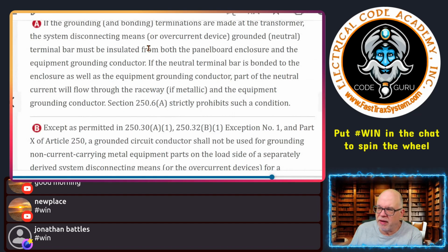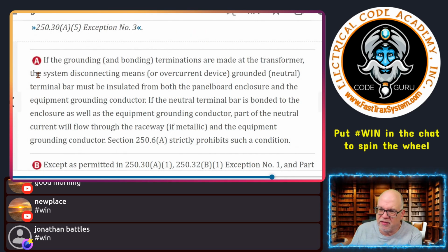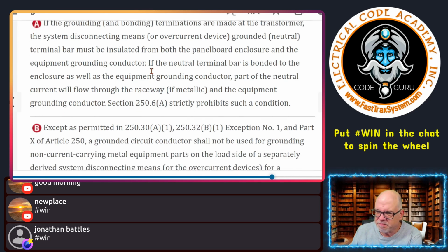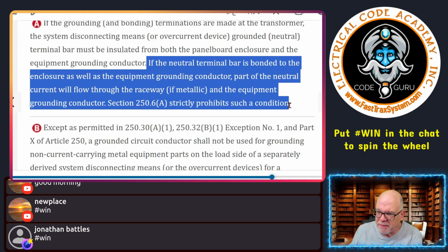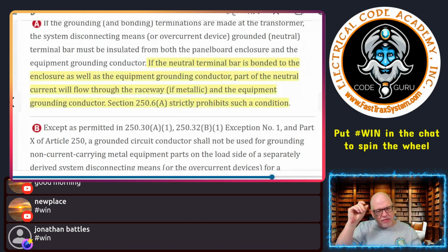It says, if the grounded and bonding termination is made in the transformer, the system disconnecting means grounded neutral bus must be isolated from both the panel board enclosure and the equipment grounding conductor. So it's isolated. Y'all got that. We just covered that. Okay. Again, if you do it improperly, somebody asks what happens. What if I accidentally leave the green screw in the panel bonding the neutral to the enclosure, and then down into the transformer, I put in the system bonding jumper? Well, what's going to happen is you're going to get circulating current. And that's going to be a violation of 250.6(A), and it's a prohibited act. So the code mandates that we remove that scenario. So the simple task is to remove the green screw that's in the panel and to make sure that we isolate the neutral. Okay, makes sense?